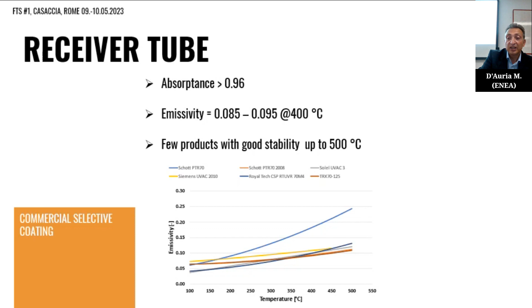Only a few products on the market, Schott PTR 70 and UVAC 3, are suitable for high temperature, above 500 degrees, for application with molten salt as a heat transfer fluid. So the only coating with known photothermal performance at 550 degrees and proved thermal stability for a lifetime of 25 years has been developed by ENEA, using the technology of double nitride cermet acquired and commercialized by Archimedes Solar Energy.